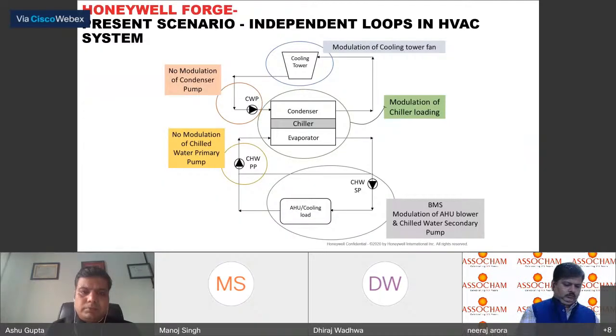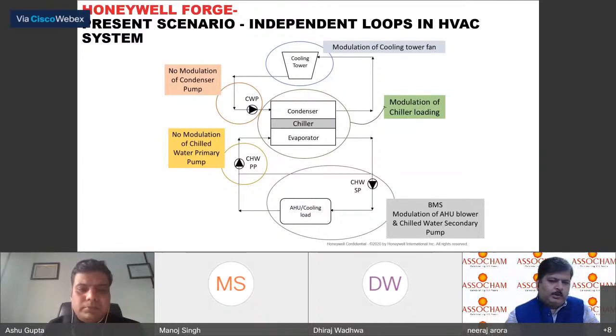So now I was talking about Honeywell Forge. This is a platform—this is the conventional system. Somewhere you have a BMS system, it talks to your chilled water, secondary pump talks to a pump, and your AHUs, your two-way valves will be there in the AHUs. You'll have two-way valve modulation, and the secondary pump modulates based on the back pressure or the pressure you want to maintain at extreme AHUs.